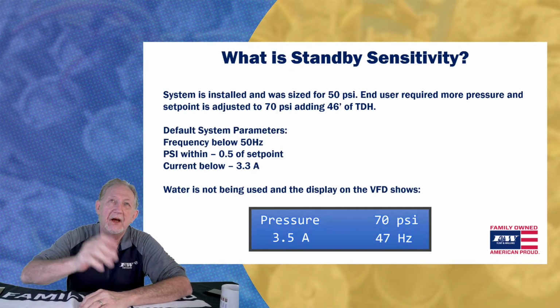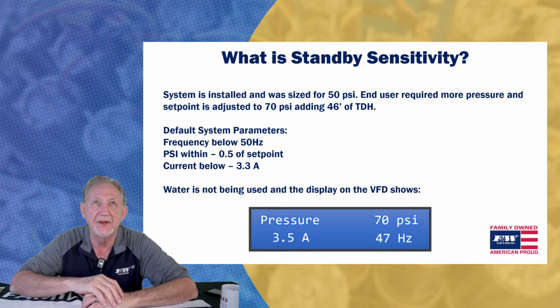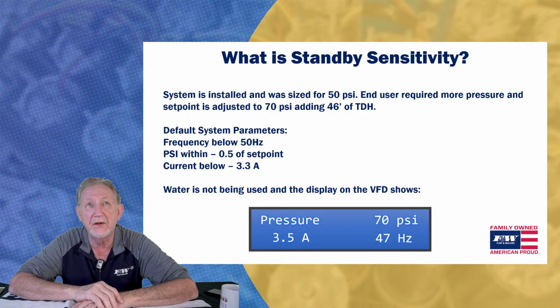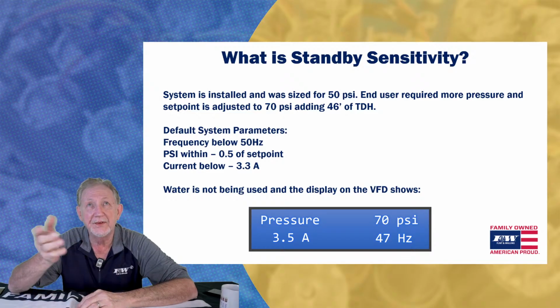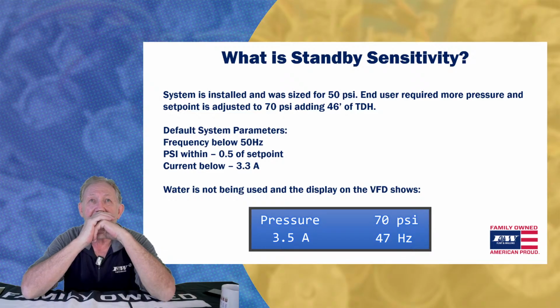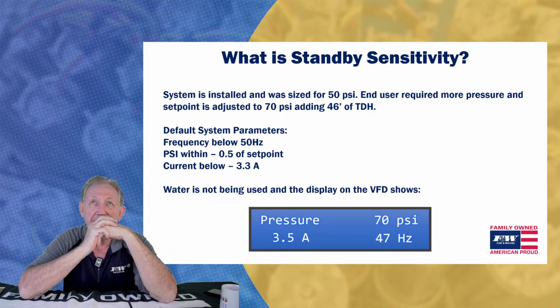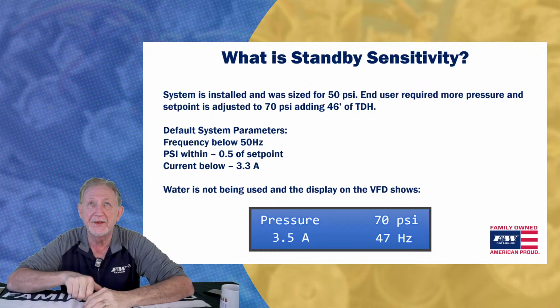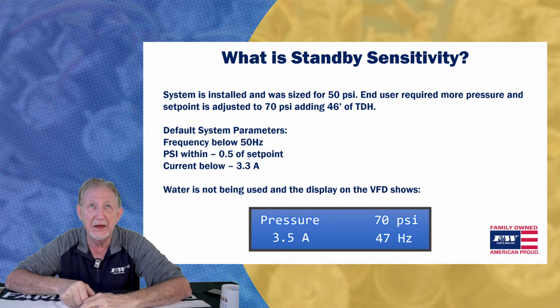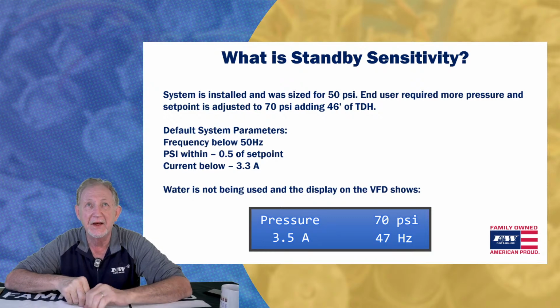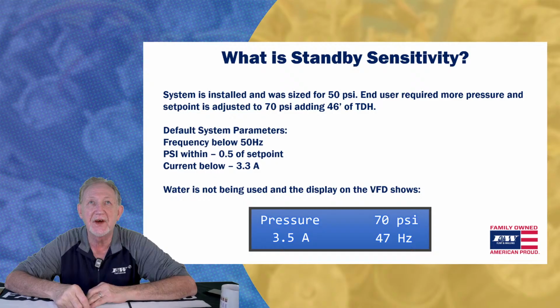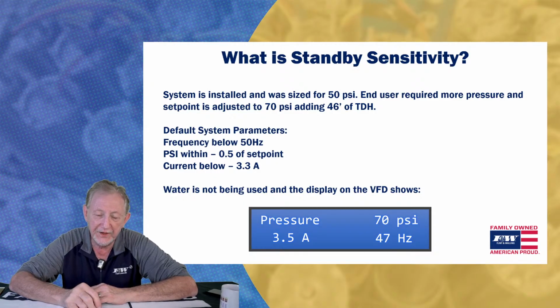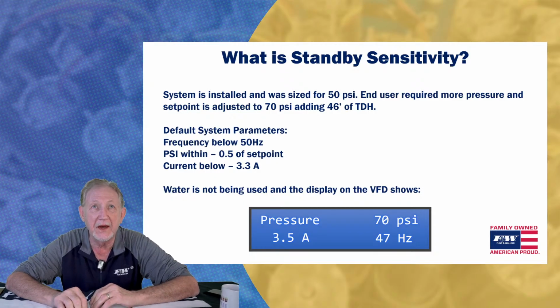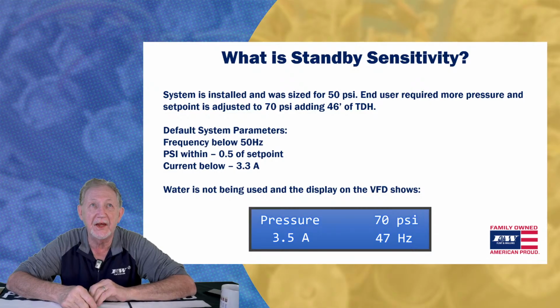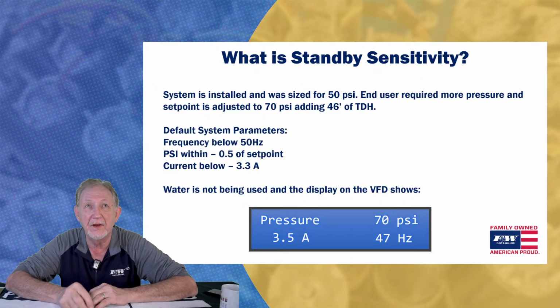All right, so as we wind down this session, I wanted to circle back on this underload and this sensitivity. Let's look at this here. System is installed and was sized for 50 PSI. But the end user at some point decided, I want a higher pressure, right? So they went ahead and adjusted that pressure up to 70 PSI, which added another 46 feet of total dynamic head. They did not, on the other hand, change that current down there.